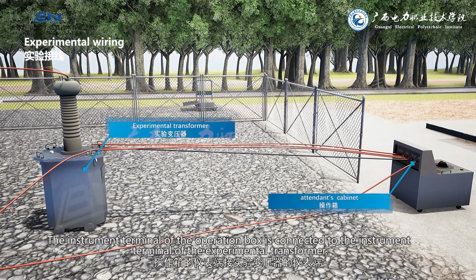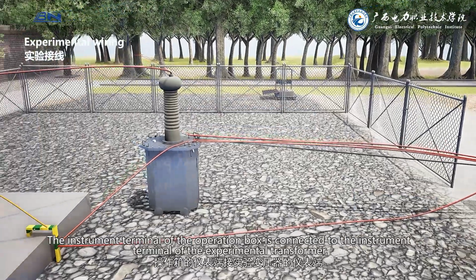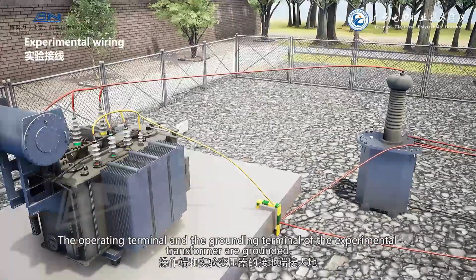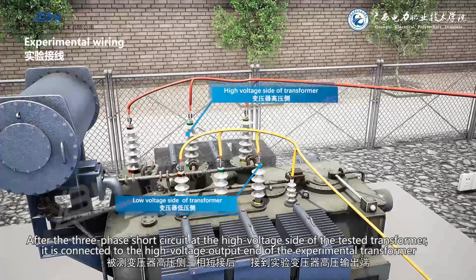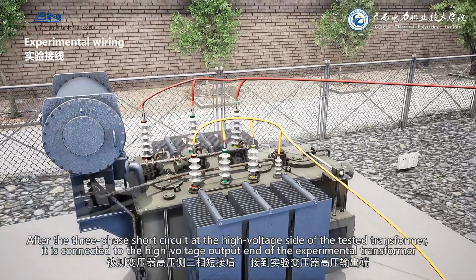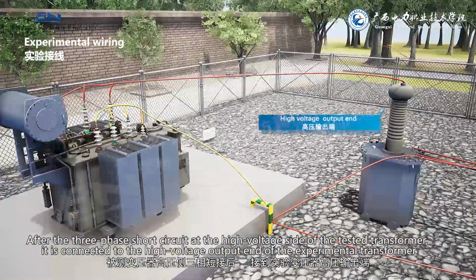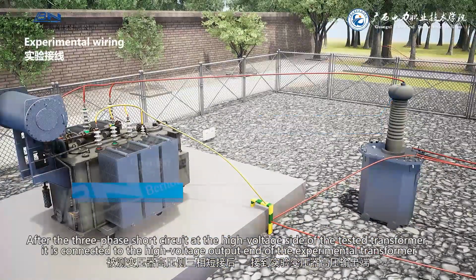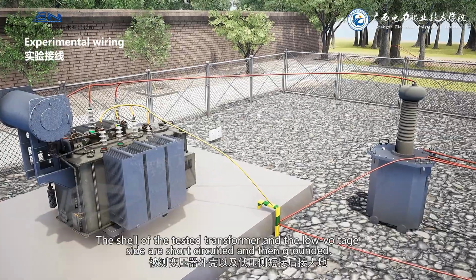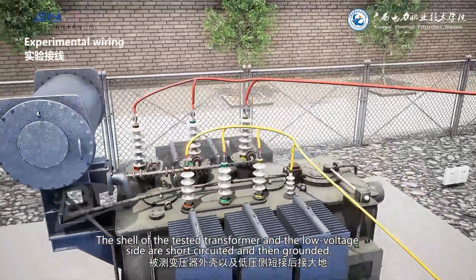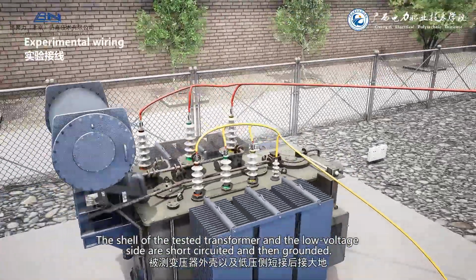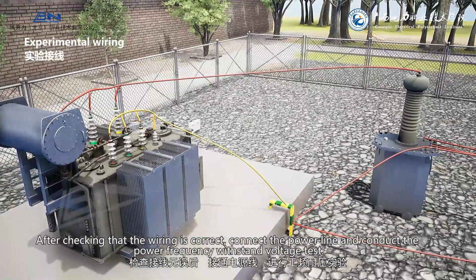The instrument terminal of the operation box is connected to the instrument terminal of the experimental transformer. The operating terminal and the grounding terminal of the experimental transformer are grounded. After the three-phase short circuit at the high voltage side of the tested transformer, it is connected to the high voltage output end of the experimental transformer. The shell of the tested transformer and the low voltage side are short-circuited and then grounded. After checking that the wiring is correct, connect the power line and conduct the power frequency withstand voltage test.